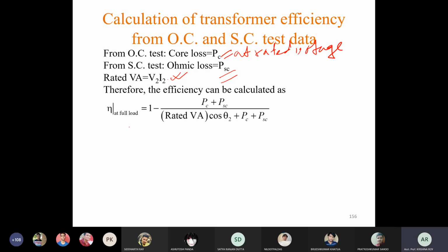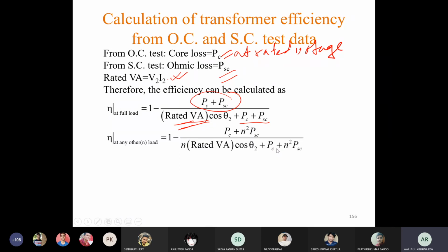Efficiency at full load is equal to 1 minus the sum of the two losses divided by input. Rated VA is from the nameplate, and the power factor will be given. So rated VA into power factor is the output, plus the two losses is the input. So 1 minus losses by input. Okay, so using this formula you can calculate efficiency at full load.